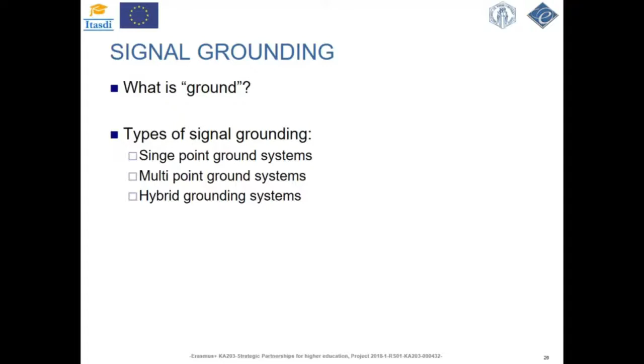Usually the grounds fall into one of two categories: safety ground and signal ground. The difference is that the safety ground is usually at earth potential, whereas the signal ground may or may not be at earth potential. Now the signal grounds can be subdivided into three categories: single point grounded systems, multi-point grounded systems, and hybrid grounded systems. However, in all three categories, we have to consider two key points: all conductors have finite impedance consisting mainly of resistance and inductance, and two physically separated ground points are usually not at the same potential.